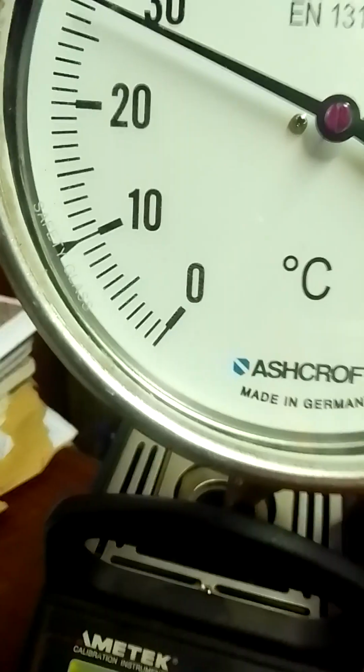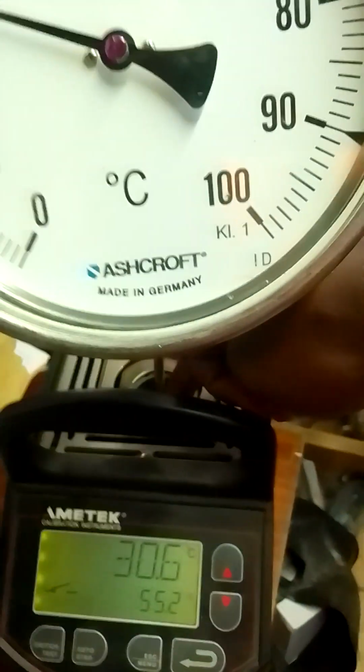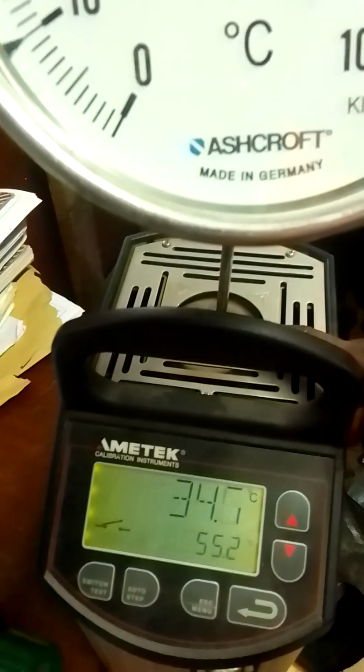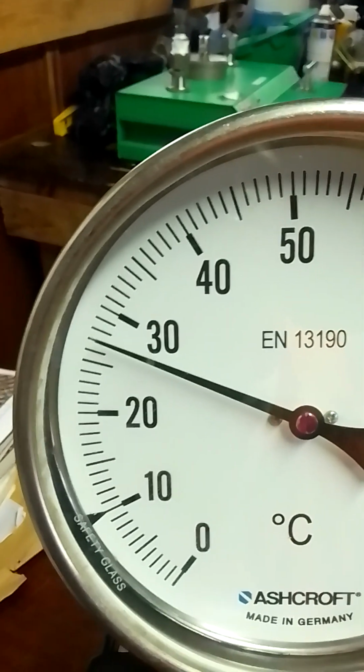The temperature of the thermowell has started changing. Formerly it was 28.1 degrees. That was the room temperature, and that is exactly the room temperature inside this well. Immediately our temperature starts increasing, the well starts increasing. You see here it's increasing now. But the gauge is not increasing because the temperature is not yet enough.